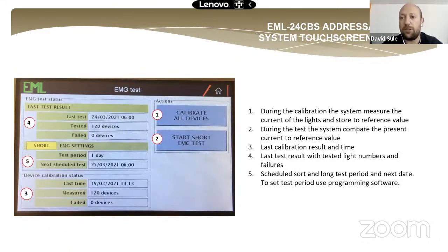We have an emergency test menu point from the LCD. As I said, during the commissioning, we have to calibrate all of the luminaires. All of the luminaires need to get a reference value during this calibrating, and we can set up automatic testing for the system. It can be a short test. This is a function test.